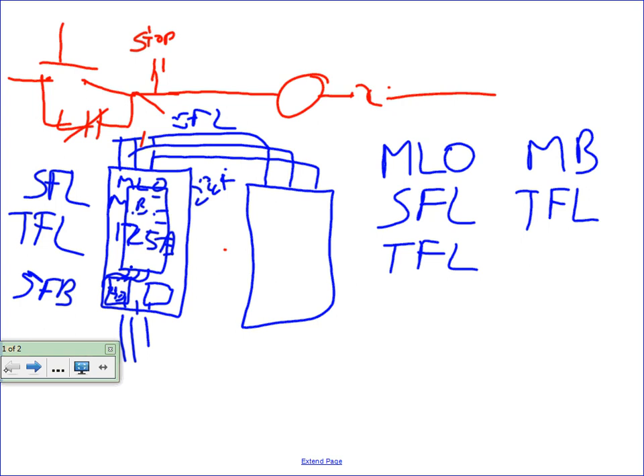So fully rated means everything in that panel is rated for the available fault current. Series rated means it's a tested combination. Probably the main's rated for the fault current, but the branches aren't. And again, if you have a fault with the series rated panel, it's a good chance you're going to lose the whole panel, because the main's going to take the fault out. Okay. On a fully rated panel, you still could take out the whole panel, but you have a better chance that maybe the 20 amp breaker feeding the outlet where the fault occurred trips, and you don't lose the whole panel, just that circuit, right? So for hospitals and data centers, you probably don't want to look at series rated product. You want to look at fully rated. But for schools, malls, stuff like that, this is probably a good place to look for series ratings, because it's going to save you a ton of money.